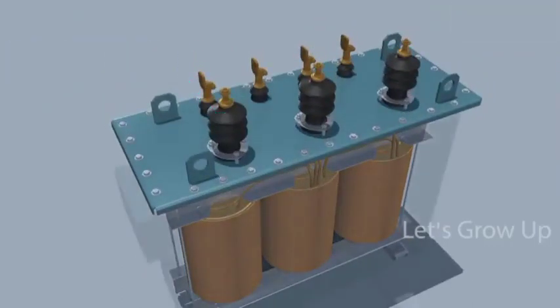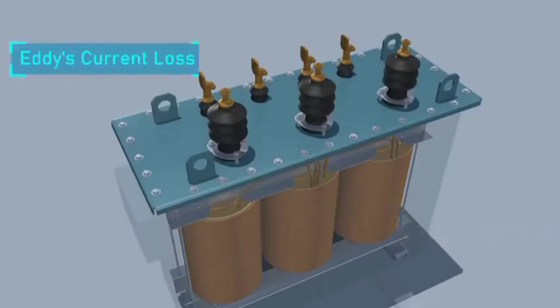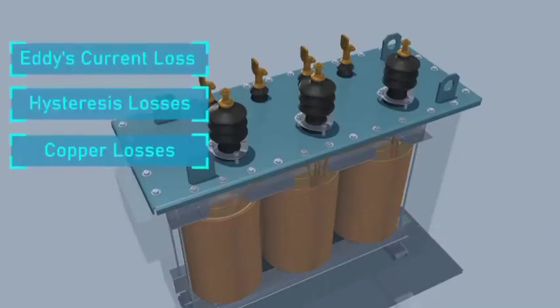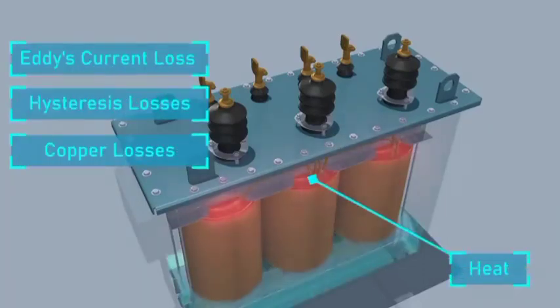During its working or transferring the power from the primary to the secondary winding, various energy losses happen like eddy current losses, hysteresis losses, and copper losses. All these losses generate heat. To prevent heat, transformer oil is used inside the tank.